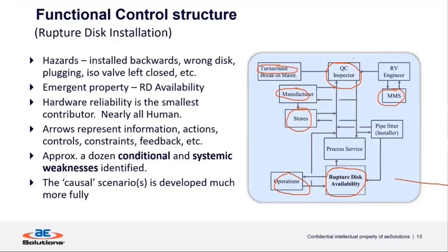So recommendations were made around technical training for the role, authority to act, communication requirements with all the different people that had to have been talked to, controls around who is allowed to fill into the role. Those were some of the findings from this STPA study using this control drawing. So a lot of value was added because you do see this periodically. I'm sure many of you on the call have seen these things happen, and we're working to minimize that, to identify weaknesses, latent conditions before something bad happens.